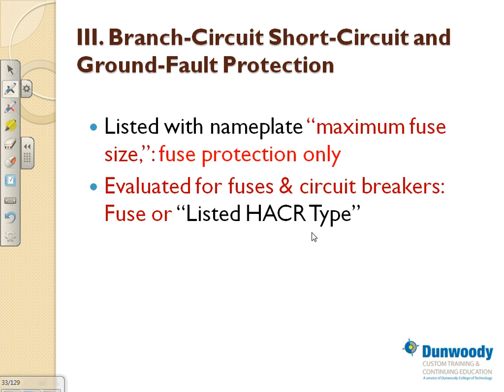That's what we said, guys. When you have an overcurrent protective device for the chiller, it's going to be the maximum fuse right on the nameplate. And if it's a circuit breaker, it will say HACR, heating, air conditioning, and refrigeration type. Almost all the circuit breakers, if you look at them, say HACR on them. Large circuit breakers, meaning you can use this one in HVAC equipment. Otherwise, if it's not HACR, you're not supposed to.